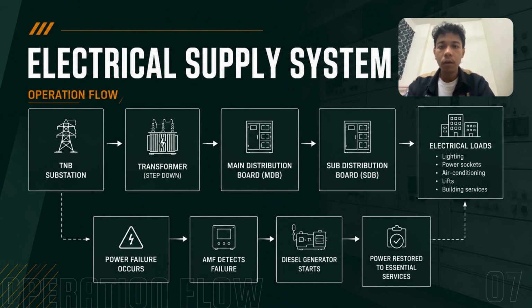However, if a power failure occurs, the automatic mains failure or AMF system immediately detects the loss of the main power supply. It then automatically starts the diesel generator. After the generator reaches stable operating conditions, it supplies electricity to the essential building services, ensuring that important operations can continue with minimal interruption until the TNB power supply is restored.